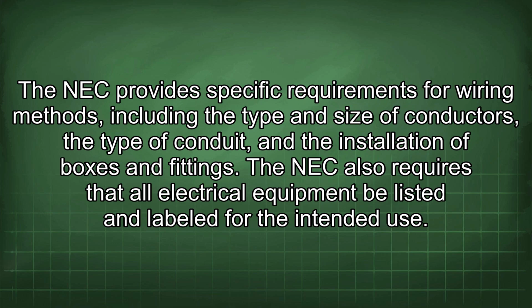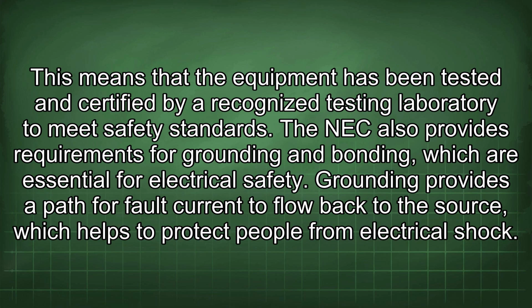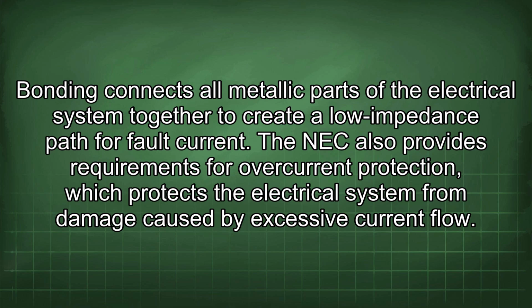The NEC also requires that all electrical equipment be listed and labeled for the intended use. This means that the equipment has been tested and certified by a recognized testing laboratory to meet safety standards. The NEC also provides requirements for grounding and bonding, which are essential for electrical safety. Grounding provides a path for fault current to flow back to the source, which helps to protect people from electrical shock. Bonding connects all metallic parts of the electrical system together to create a low impedance path for fault current.